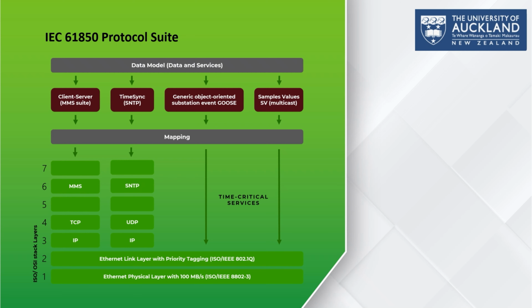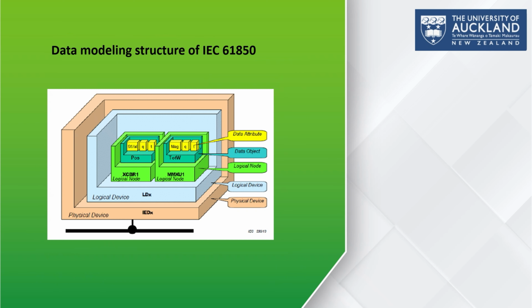So this diagram shows the hierarchical data model for IEC 61850 used in the digital substation. At the top is the physical device, an IED, which contains one or more logical devices that group different functions, such as protection or control. Each logical device includes several logical nodes. These logical nodes contain data objects like breaker position and total active power, which describe functional information. At the lowest level are the data attributes, which hold the actual real-time values exchanged during substation automation.